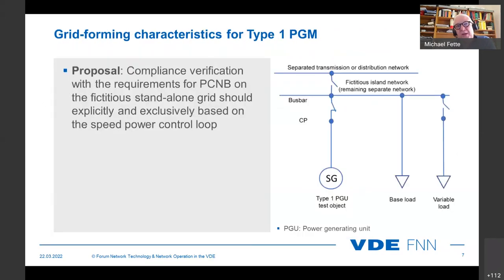Therefore, we set up a fictitious islanding network, as you see. We have a separated transmission or distribution grid, an open circuit breaker, a simulation model as a bus bar, and our test object, and the test object gets the base load and the variable load. Under different conditions, the test object must show that the controller works, that the desired damping ratio will be fulfilled, that the system is stable and that the controller works as it should. Fictitious means it is similar to, but separated from, the others. If it's a synchronous generator, it fulfills that, but we want to test the controllers.